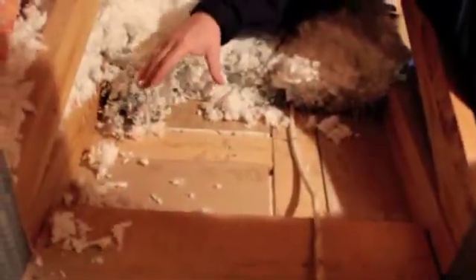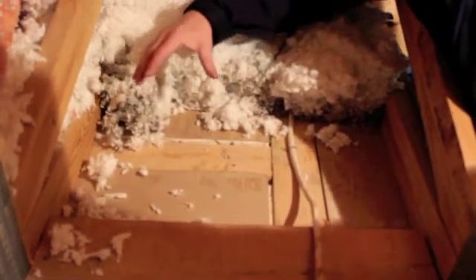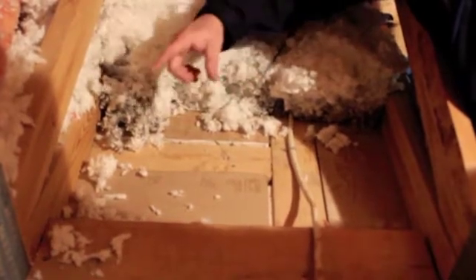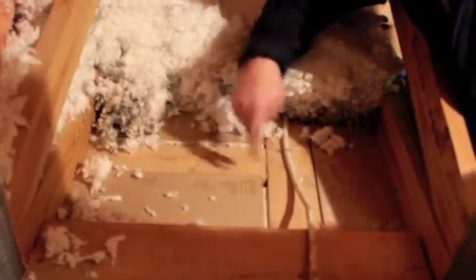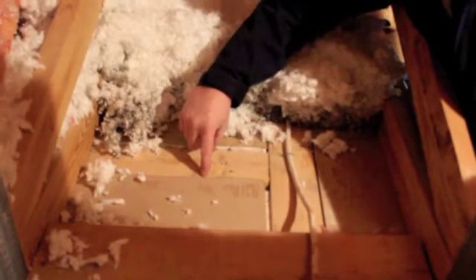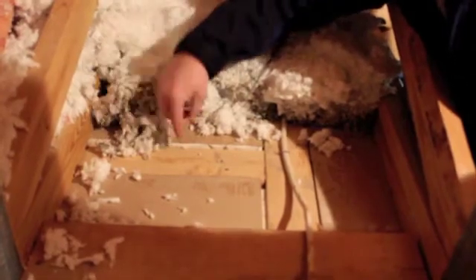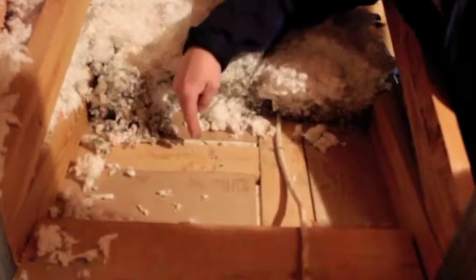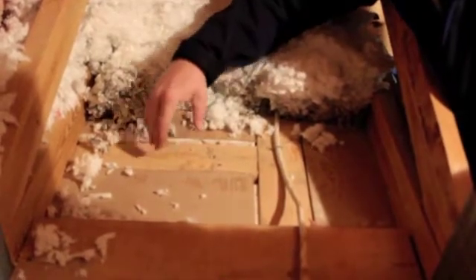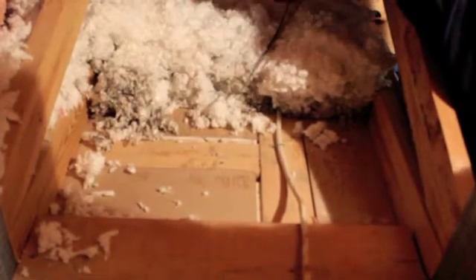What we're looking at is whether there's airflow — pathways that air can escape out of the house. The more air escapes, the more air changes in your house, and that takes your heat and cool air out. These are called top plates — the top of the framing of your interior walls. Over time they shrink and can leave a gap. This black insulation is a telltale sign that air is traveling through there, indicating a place that probably needs to be air sealed. You never want to put more insulation on something that's leaking air, because it's just acting like a big filter.